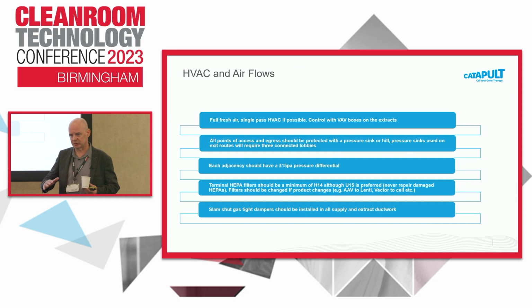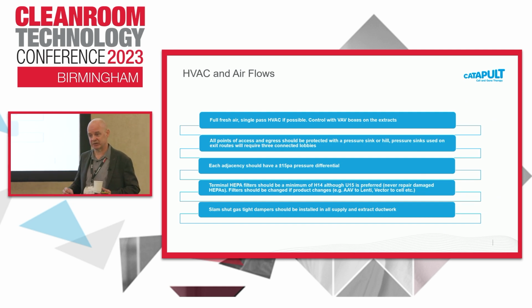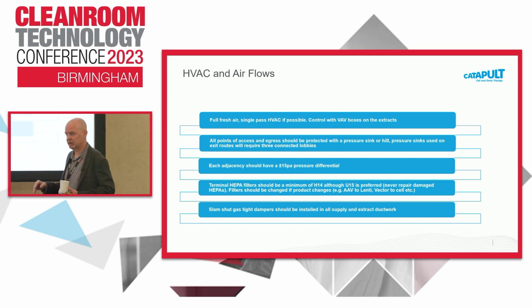As I mentioned right at the start, we're trying to do two almost mutually opposing things. Classic clean room, where you're trying to keep environmental contamination out, you tend to have a higher pressure in your core and a cascade down to lower pressures as you work your way out. With considerations for containment, you typically reverse that, and you would have the higher pressures on the perimeter, the peripheral areas of the facility, and the clean room at a lower pressure. When you're trying to do both, the best approach that we've found is at every point of access and egress into and out of that clean room, you make use of either a pressure sink, so a low pressure environment that will suck air bleeding from the clean room and from the routes in and out, or you use a bubble or a hill to effectively act as a barrier for environmental contamination moving out of the clean room and out of the route in. So either one works.